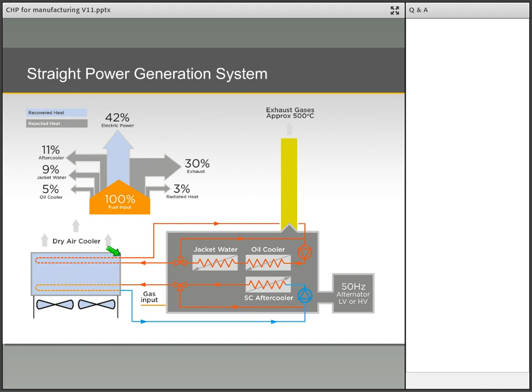Whilst the CHP system is set up to recover heat from the engine cooling circuit and exhaust gases, it can be configured to reject this heat and still allow the unit to run at full output. This may be required for a blackout scenario when the CHP is running as a standby generator, or could be a commercial decision based on the comparative value of electricity and gas. This comparative value is known as the spark spread.